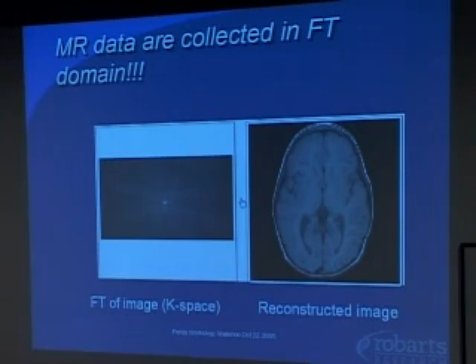And I think that because of my history of swimming in Fourier space when I was a graduate student, the whole field of MRI and CT being so Fourier based has always held a tremendous fascination for me. So there's what the raw data look like, and this is what we see. If we are collecting the data in an MR scanner, we're actually building up Fourier space line by line, or sometimes it's in spirals, or sometimes it's in lines through the origin. But in any case, every few milliseconds we're picking up a new sample in Fourier space. So the data collection part of an MR scanner is collecting these points in Fourier space, and then the reconstruction phase kicks in. You feed this data set into an FFT algorithm, and you go from here to here.